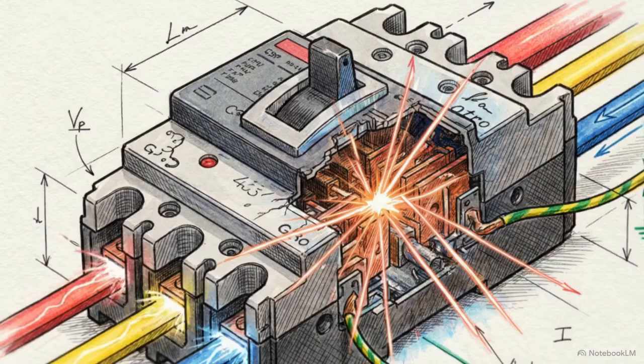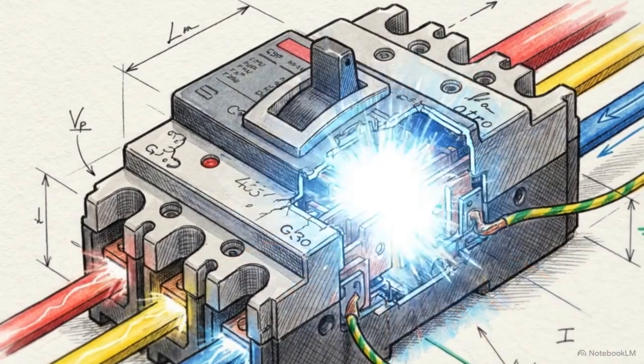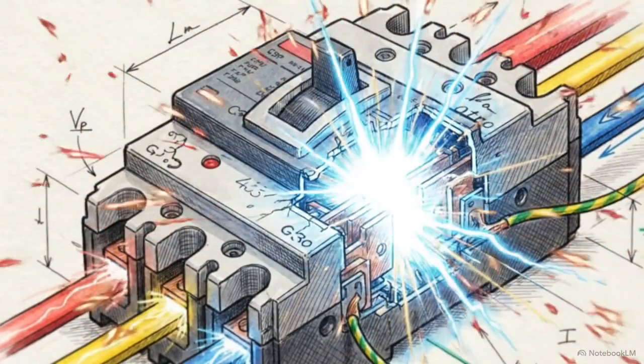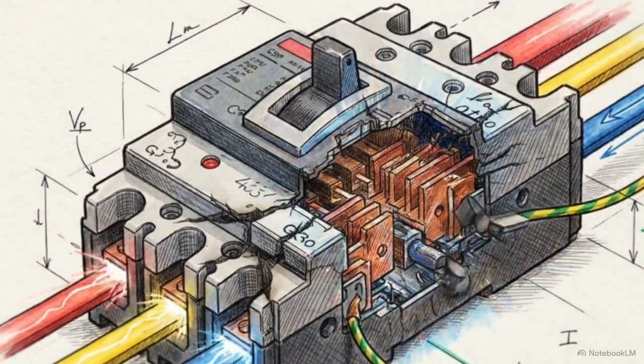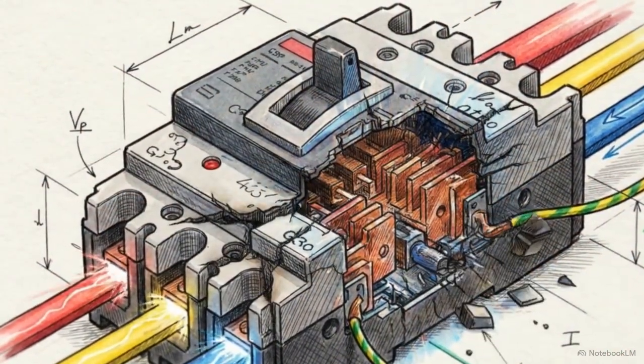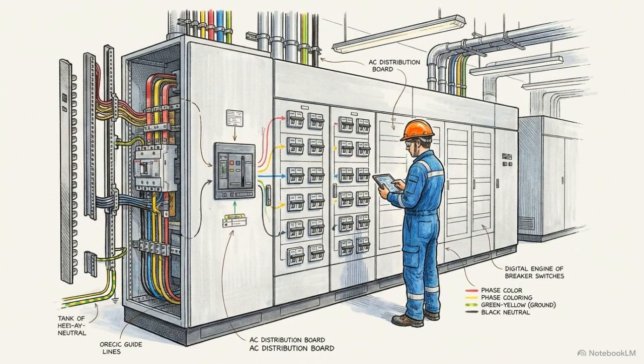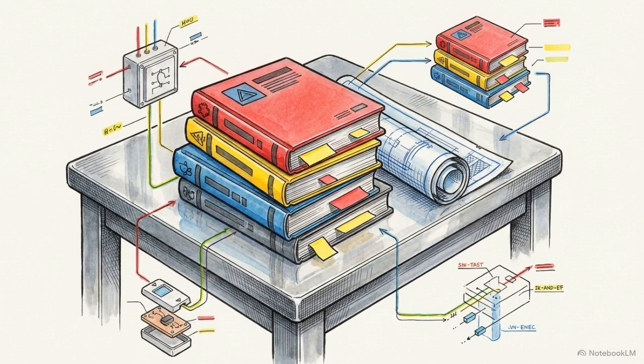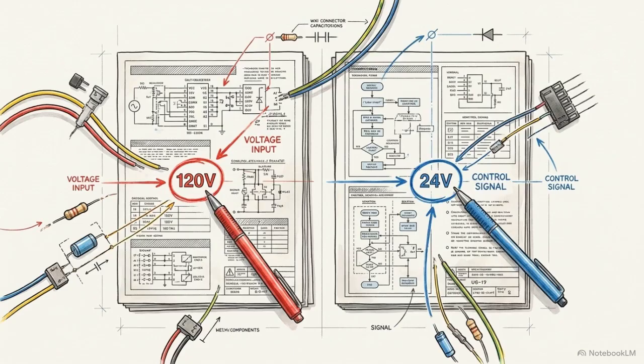If a massive industrial circuit breaker fails to interrupt a fault, the result is a sudden, violent arc flash. Connecting unverified hardware is catastrophic. An AC distribution board reaches the status of a safe grid asset only after exhaustive, mathematically verifiable testing proves its operational readiness. To prove that safety, commissioning engineers evaluate the equipment against manufacturer manuals, project specifications, and global standards like the IEC or IEEE. But these documents frequently conflict.